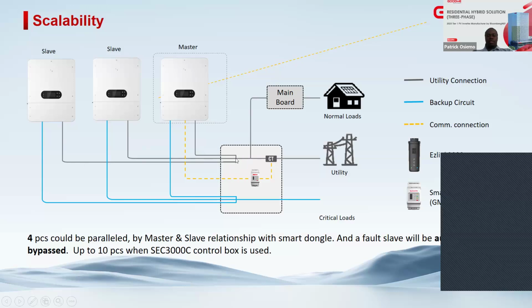This on-grid port has to be monitored to prevent export to grid, and also to monitor the consumption from the grid. So we have CTs right on the incomer line. The CTs can either connect directly to one of the inverters. If the inverter is too far, then you have a smart meter in between: CT to smart meter, then smart meter to one of the inverters. One of the inverters, because if you're doing 1 to 4 pieces, then one inverter can be a master. The rest of the inverters become slaves.